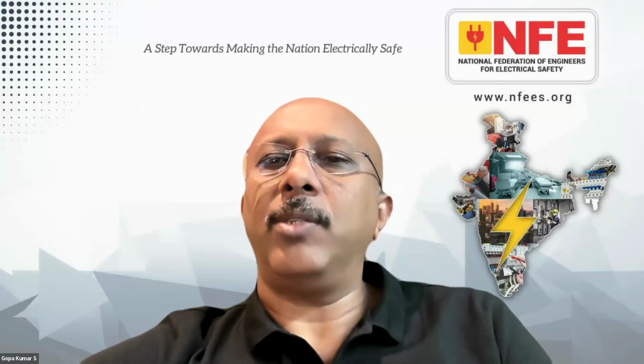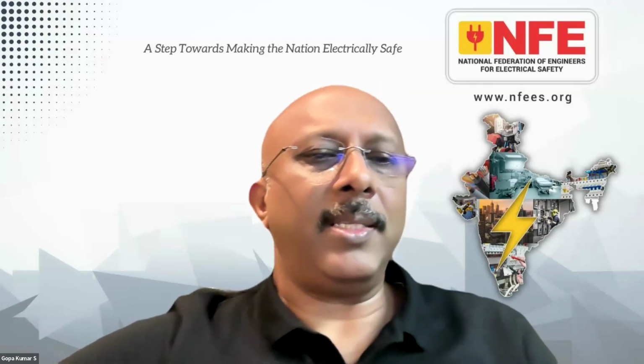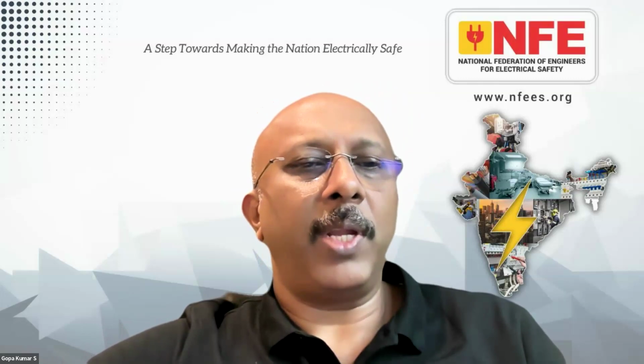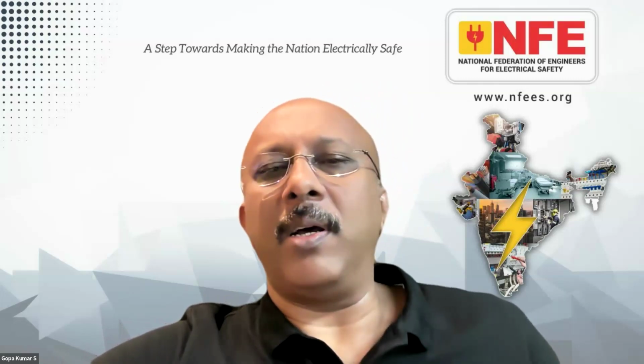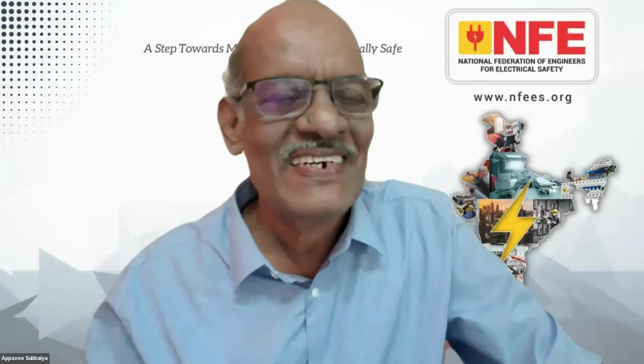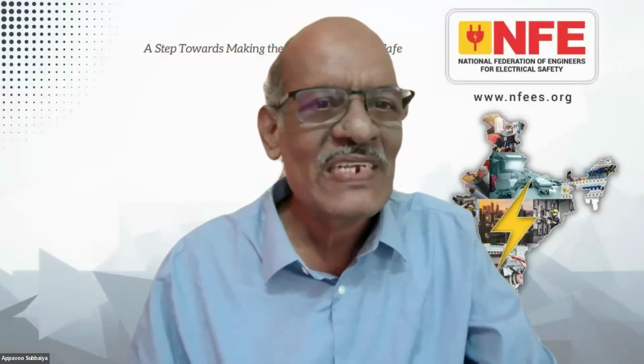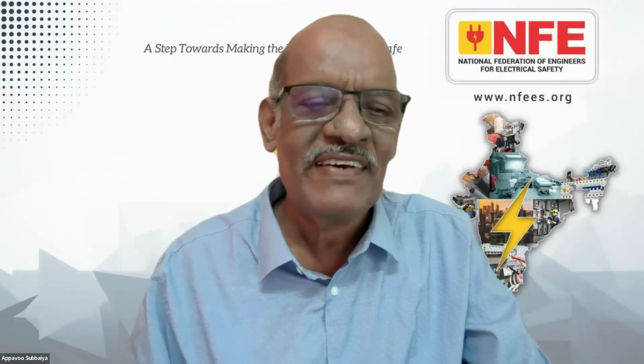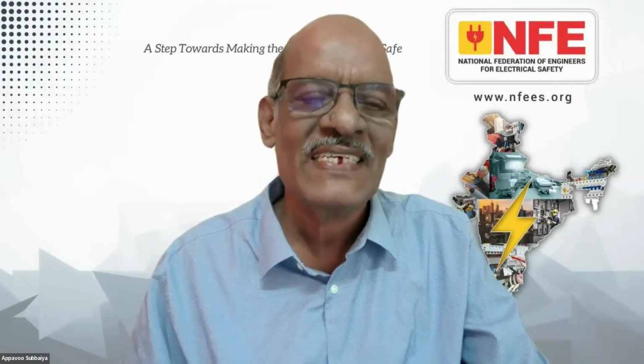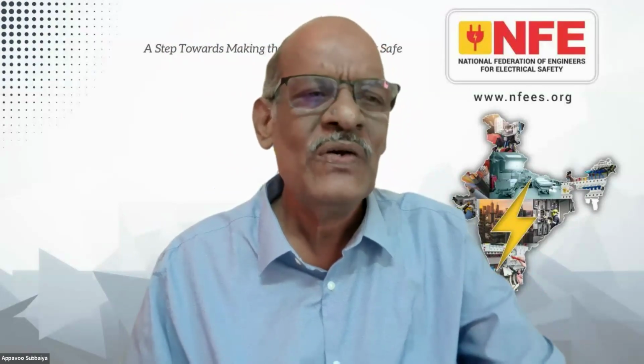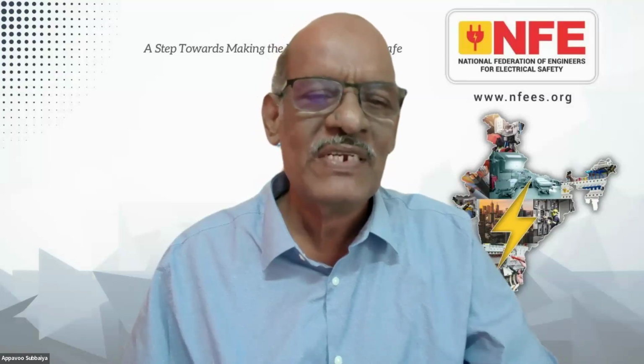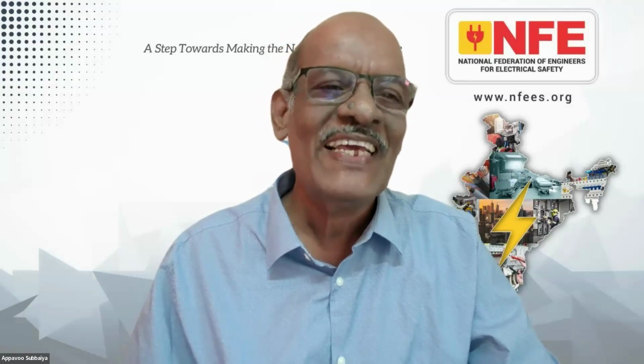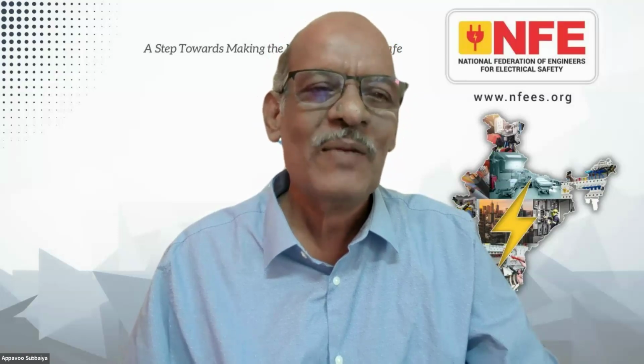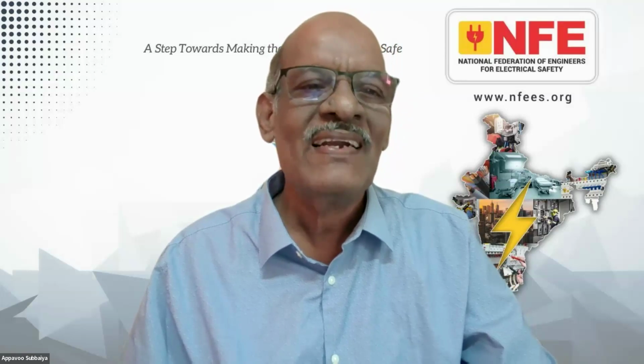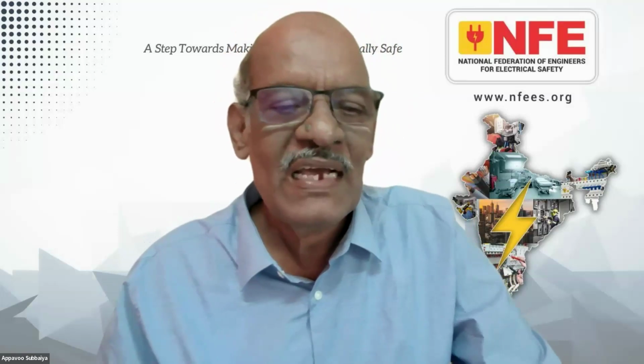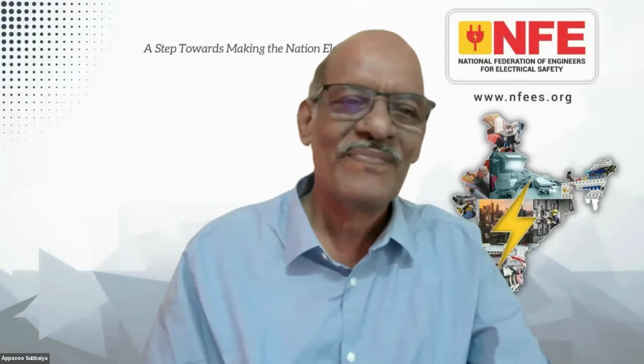Next, Mr. Sanjeev Kumar says that they are using this paint extensively and it is also approved by the electrical inspector. Appavo sir, any comment on paint for insulation instead of rubber mat? It is the same question you have already answered. Nowadays it is not a rubber mat, it is an insulation sheet. Previously there were rubber mats of very high thickness. They were very tough to transport and would crack within a year. So now they provide rubber sheets with very good dielectric strength. If you want to provide any coating, it is up to you, but it is not mandatory. You provide the mandatory provision first, then you add the additional provision. Providing paint is not mandatory. The sheet will do.